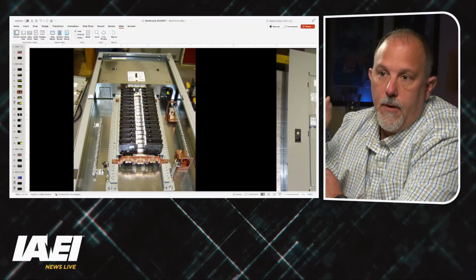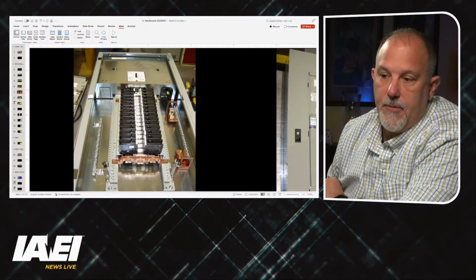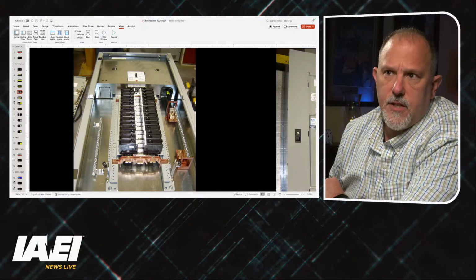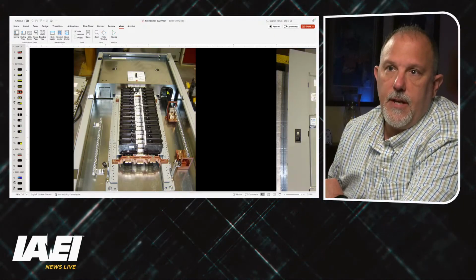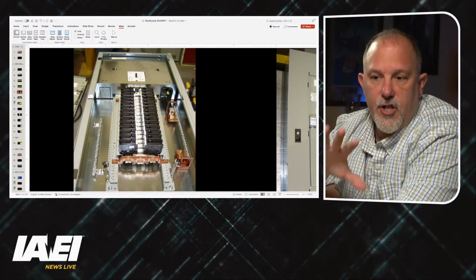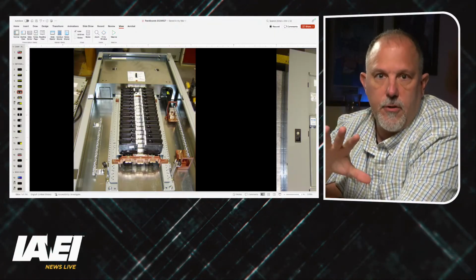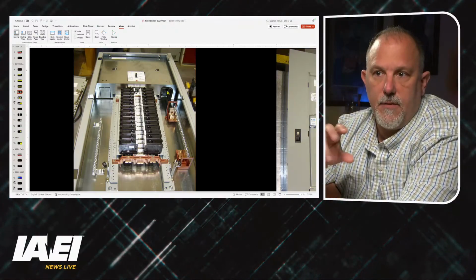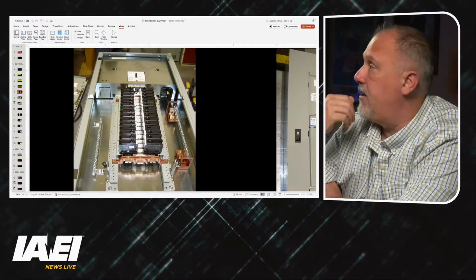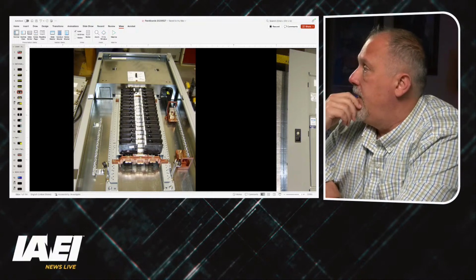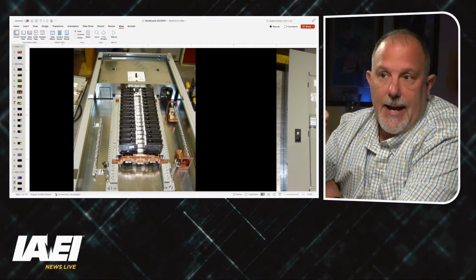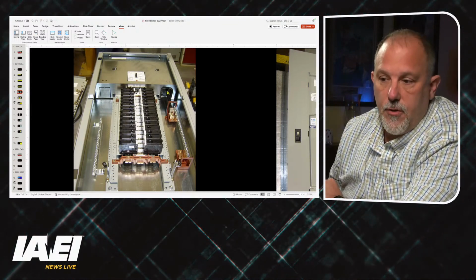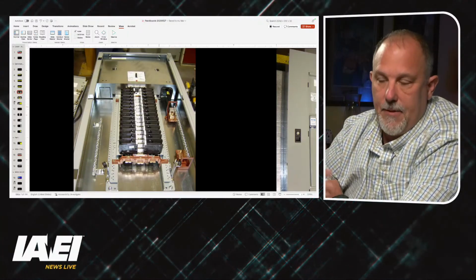So the piece of equipment I'm showing on screen here is the internal bus and structure that holds the overcurrent protective devices. That's technically the panel board. And it's designed to be placed in a cabinet, so this metal enclosure on the outside is my cabinet.